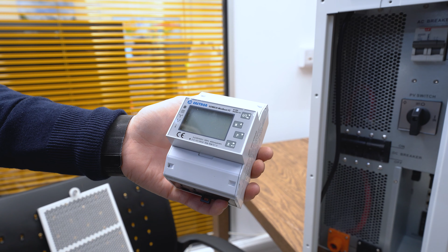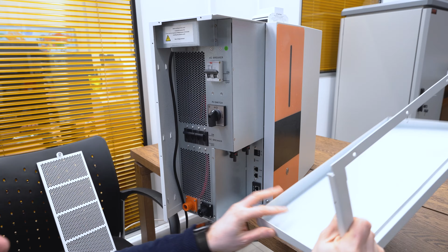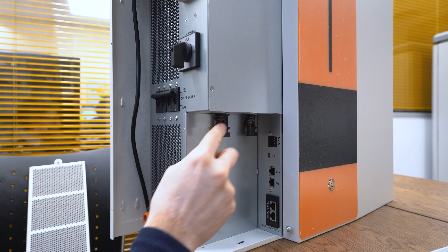All the hybrid systems are required by the law to have an extra energy meter for controlling the power flow. I'm going to remove the front cover of the inverter to access the power and communication terminals. And we can see here the solar inputs. We have two independent MPPT chargers rated at approximately 3.5 kilowatt each. We have the COMS, the BMS for your lithium-ion battery, and the Modbus communication for your energy meter.